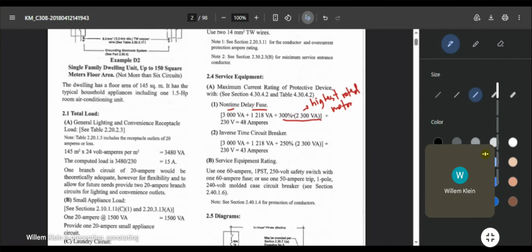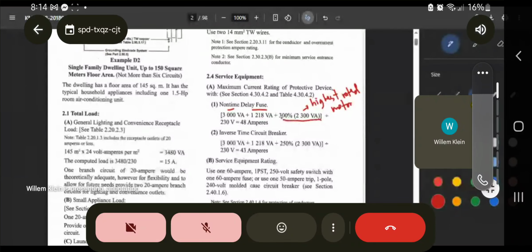Will we still use them in the computation? The answer is yes. So you will include them in this part. Okay. So what do we do with the highest rated motor? We compute it multiplied by 300%. And then the rest of your motors, you just include their rated VA. But for your highest rated motor, you will use the multiplier of 300% for the fuse. For the circuit breaker, by the way, let's complete the equation here.